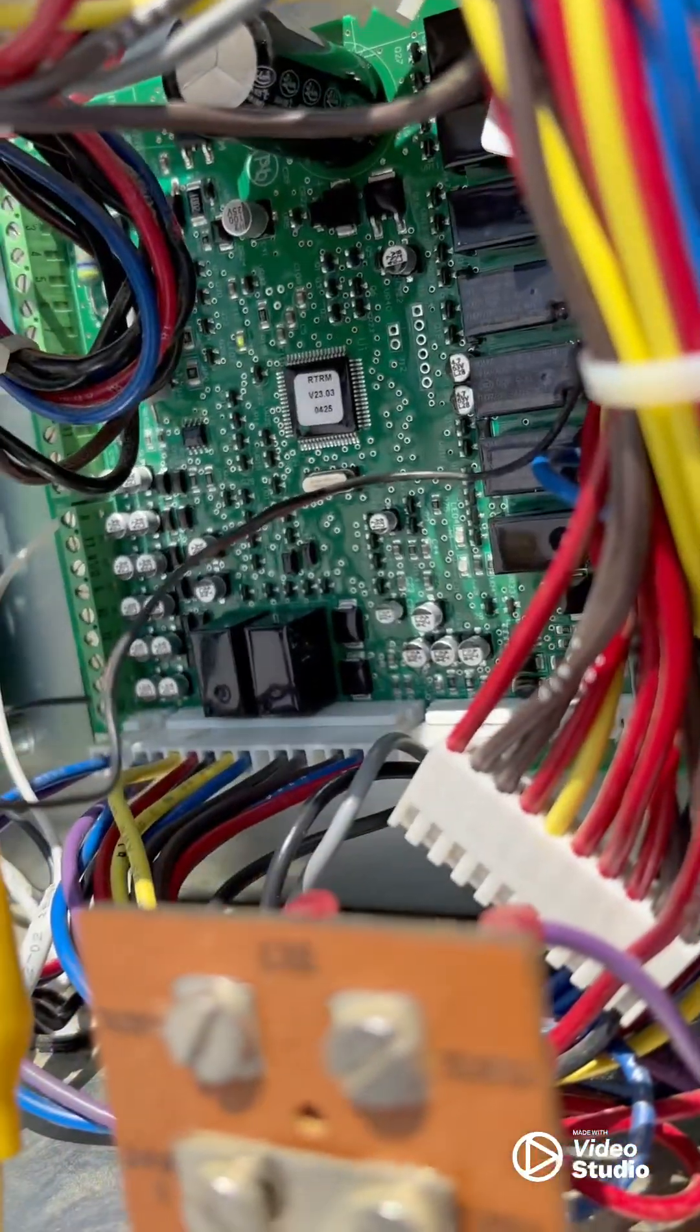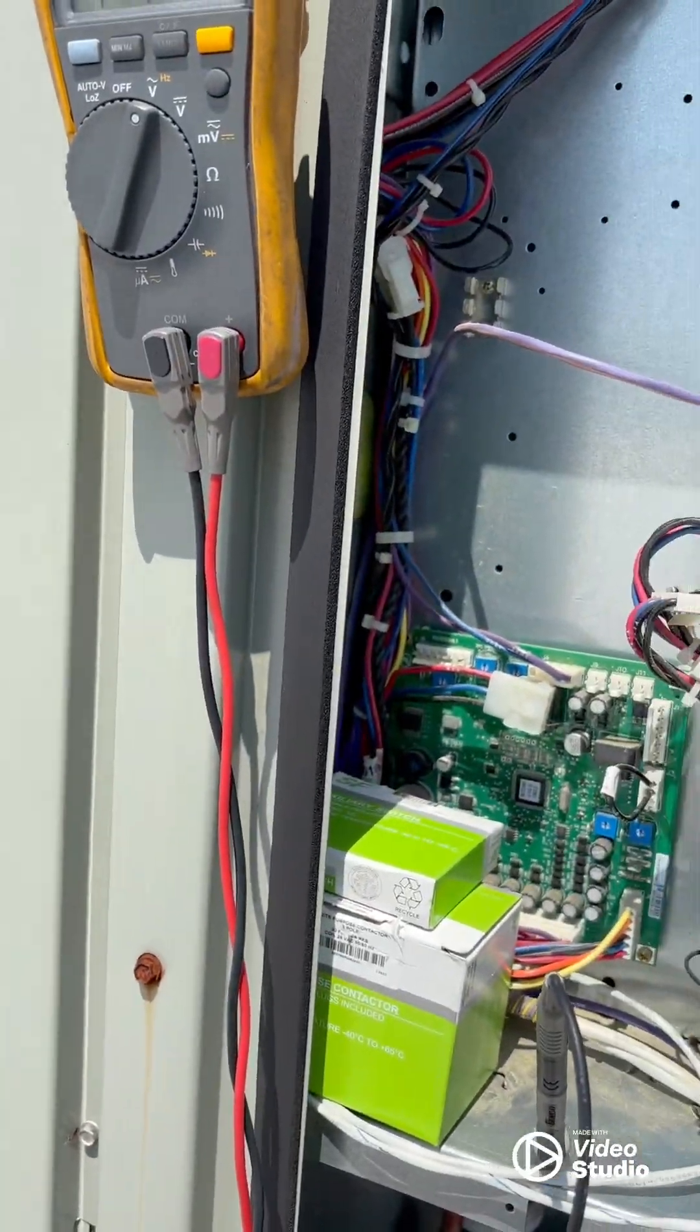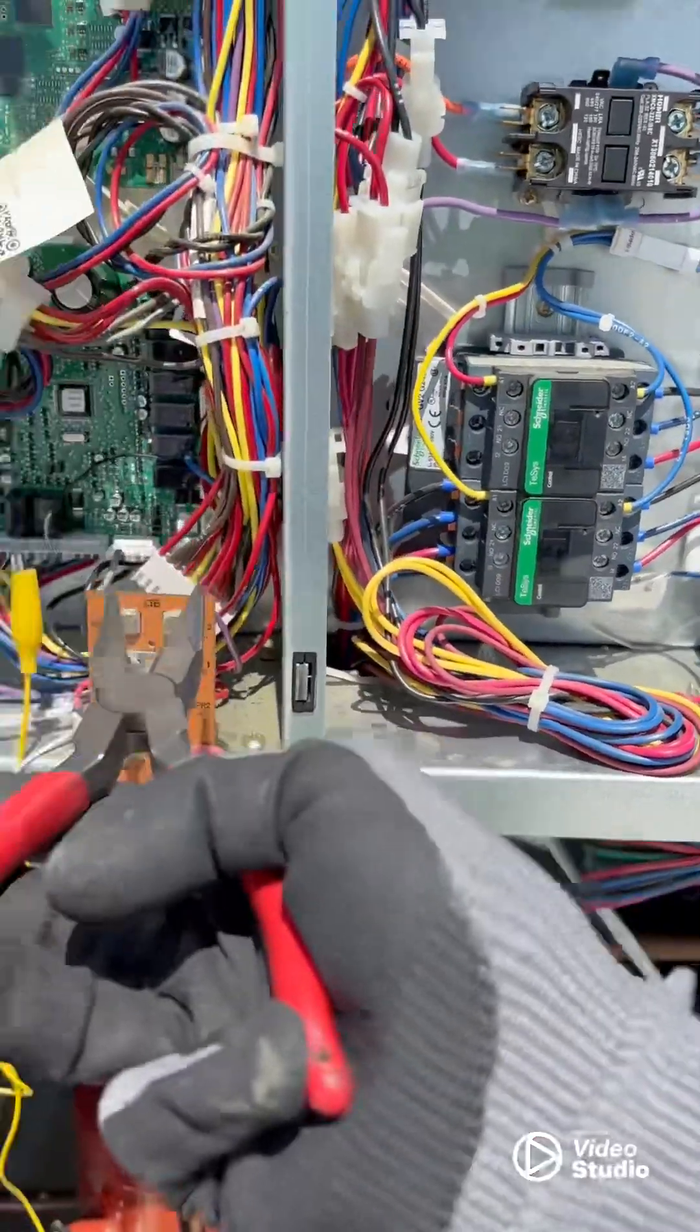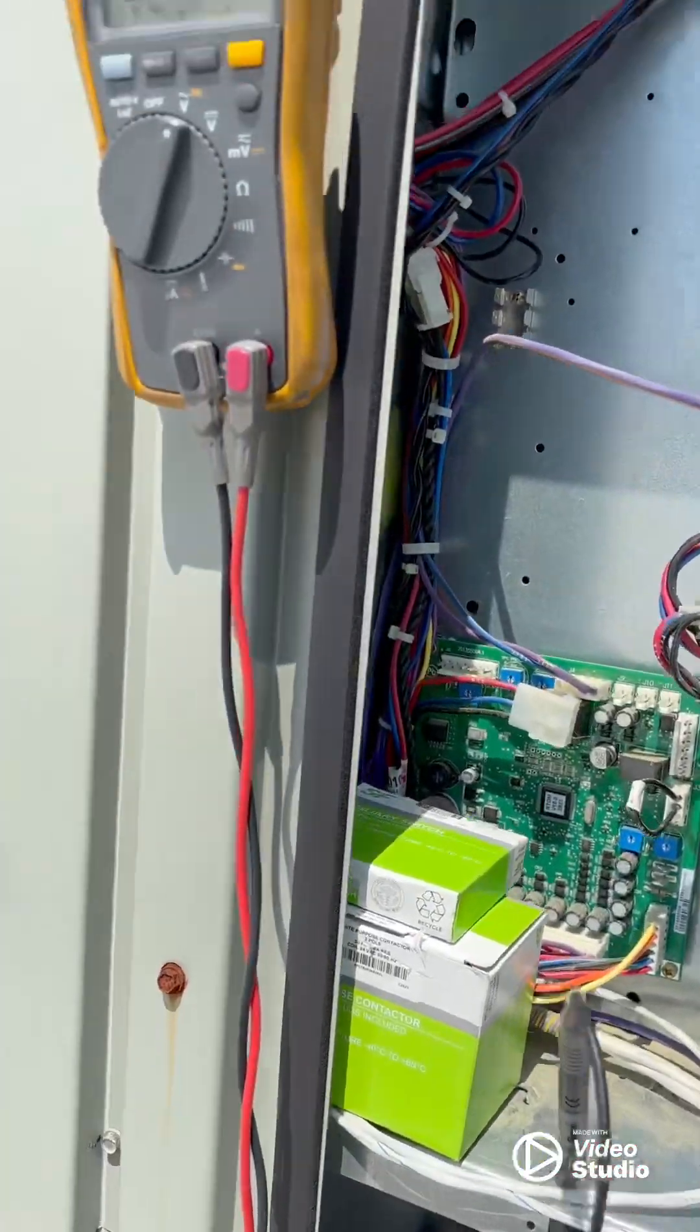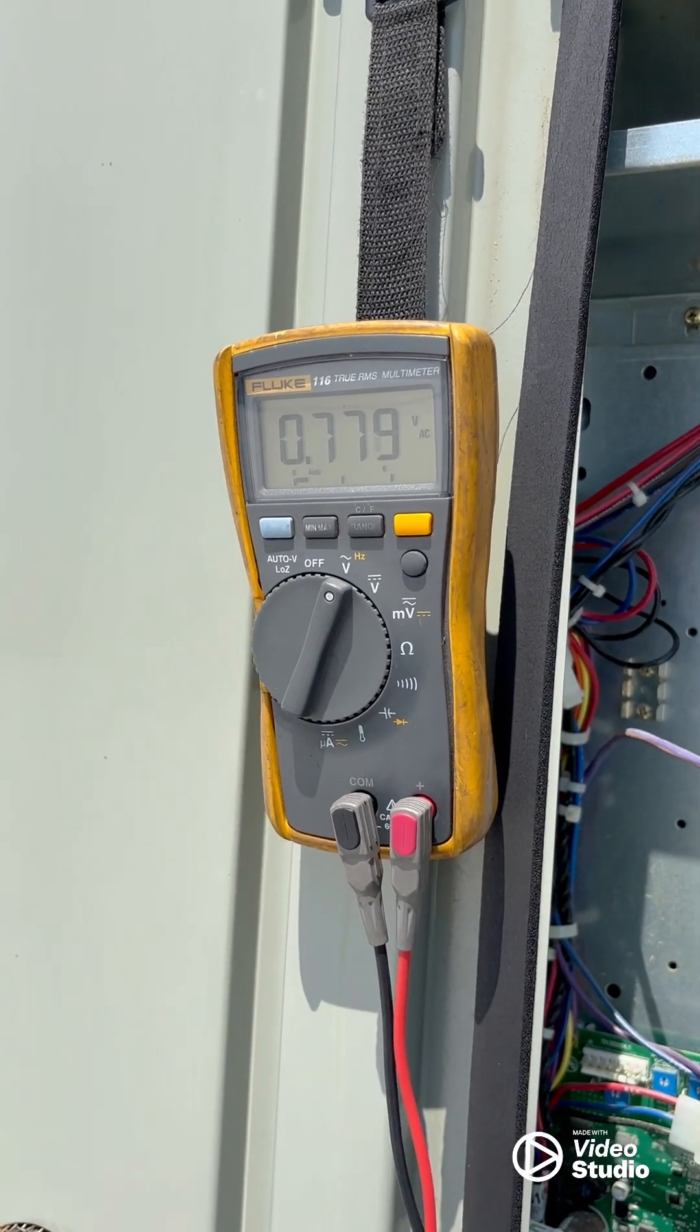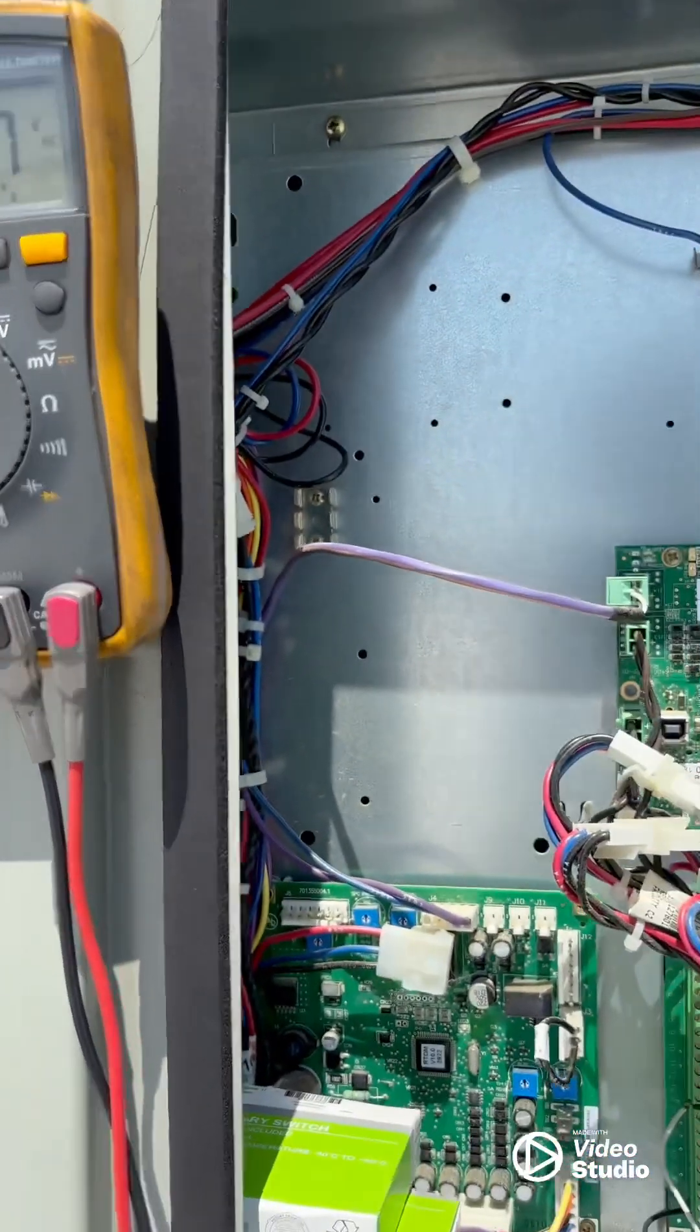We just started it up. Test mode blinking. That compressor, that contactor should stay energized and that compressor should stay on. And I should have voltage coming out now. Yep.